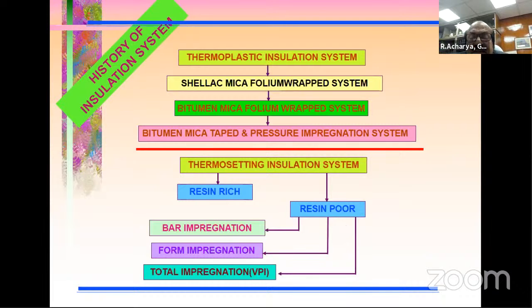Basically in the resin-poor system, which is the present practice, it is about total impregnation. It was initially bar impregnation which was practiced, maybe starting early 70s or maybe late 70s, and then subsequently form impregnation. Today, most manufacturers across the globe do total impregnation because of some of the obvious reasons of its advantage. This has not only the advantage of the basic insulation characteristic, but it has its own relevance in the present context, where it plays a very important role in the flexible operation of the machines.